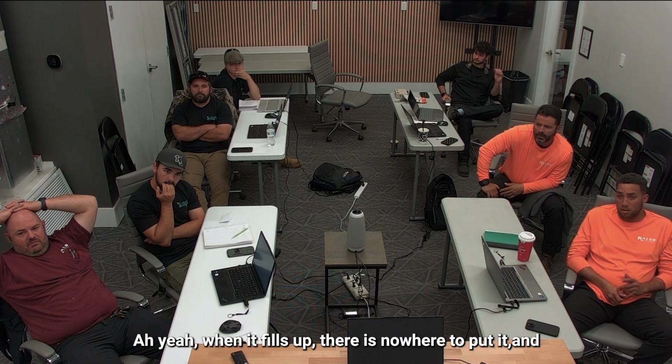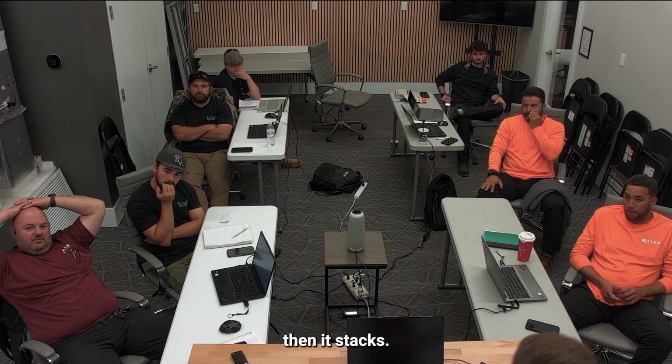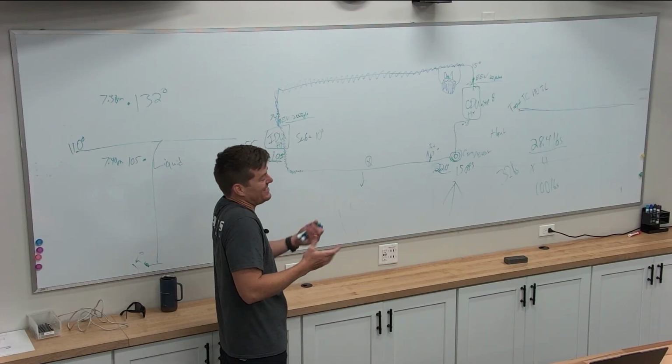Will it hold 100 pounds? Yeah. The liquid receiver on most of these units can hold 60 pounds alone. When it fills up, there's nowhere to put it, and then it stacks. So liquid is the only state. It's never not a liquid. It's always a liquid. Do you see how we got to the diagnosis on this one?